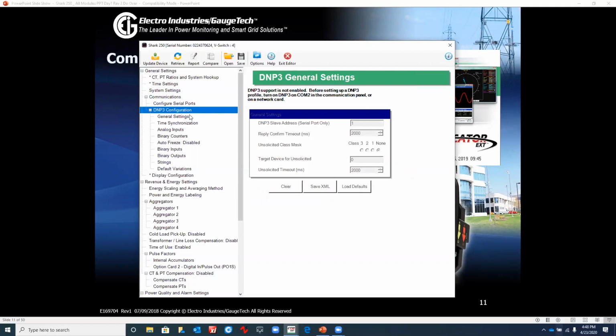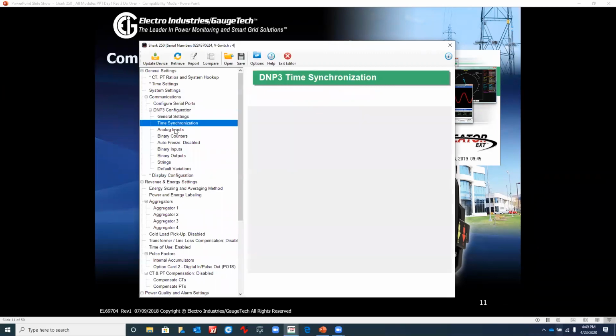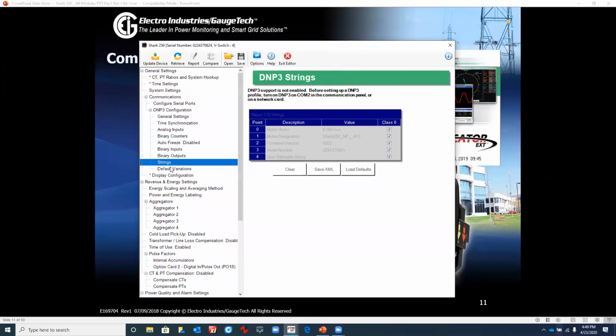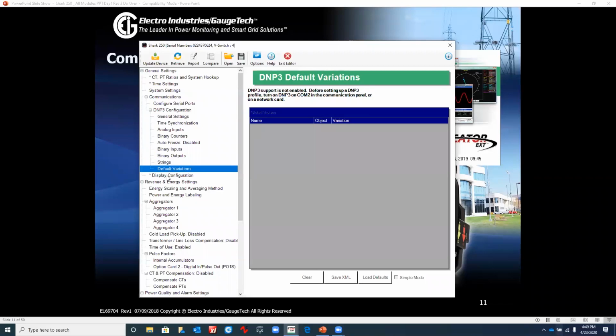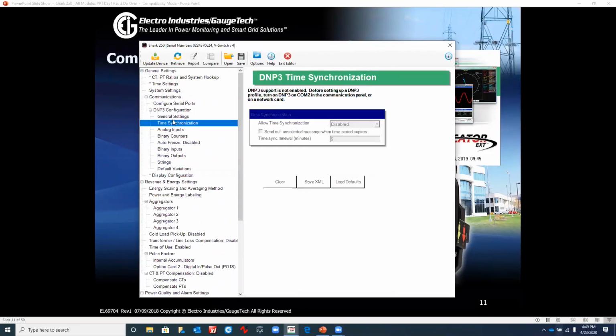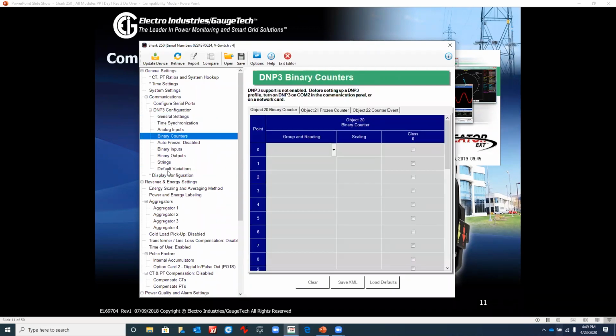We talked a little bit briefly about the DNP3. You have to enable DNP. So this is an area where you would go in and retrieve your SCADA information. Typically, the DNP setup, if it's something that you would be turning on, is usually driven by your SCADA or RTU folks, who would basically tell you you need to have this enabled so they could pull DNP from an RTU. So this is the area where you would go in and turn that on. As you go in and select, all of these are parameters associated with DNP setup. This in itself is a lengthy presentation, so it could be reserved for another time with a totally different discussion.